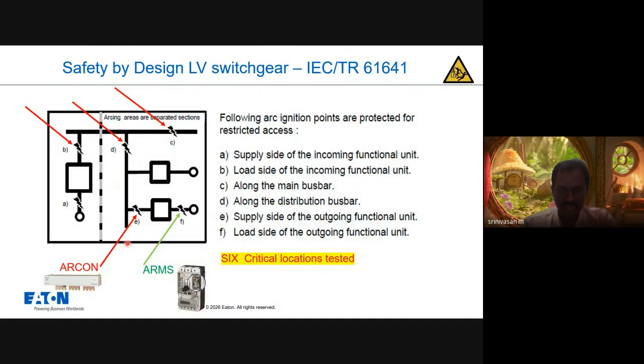Now, if you look at this slide, you can see the red color arrow marks and also the green color arrow marks. Our patented design ARCON is suitable if an internal arc happens at any of these red color arrow marked points. I will explain in detail one more time. For example, this is one of the outgoing feeder cable compartments. If the internal arc happens in the cable compartment, we don't need to shut down the main incomer, because only this specific outgoing feeder cable compartment has been affected. So the FM team can easily unterminate the cable, do the cleaning operation, terminate the cable again in the proper way, and put it back into service. This is very easy. The FM team can manage.